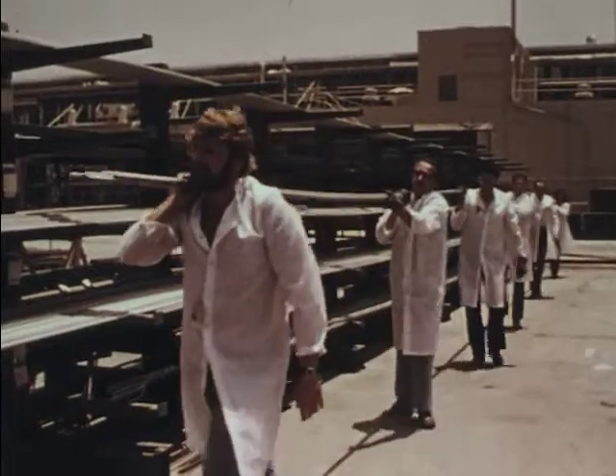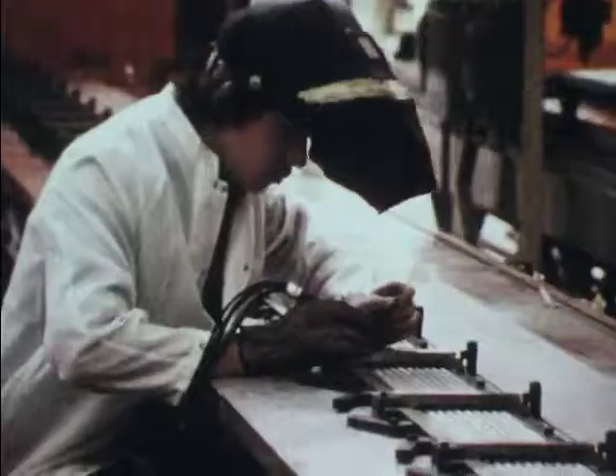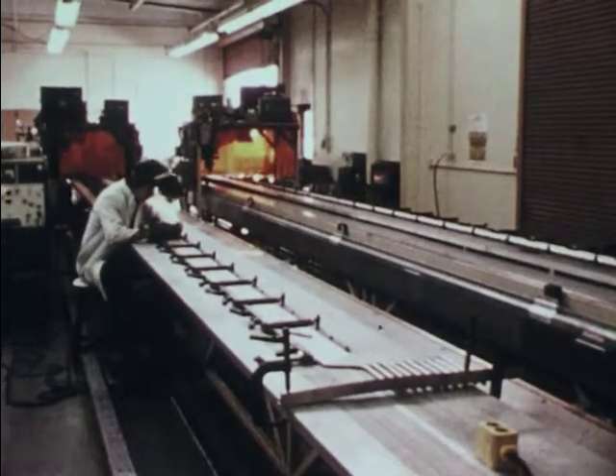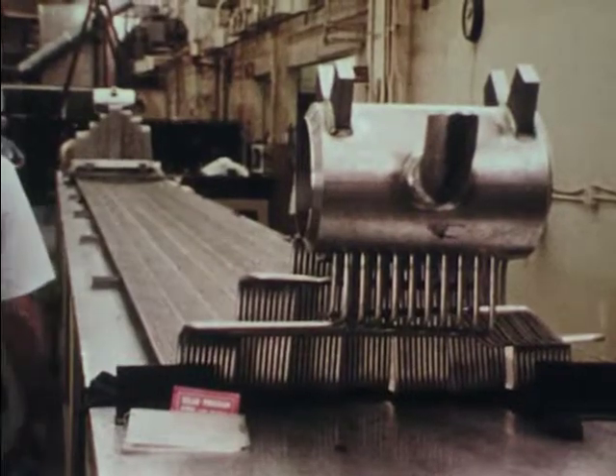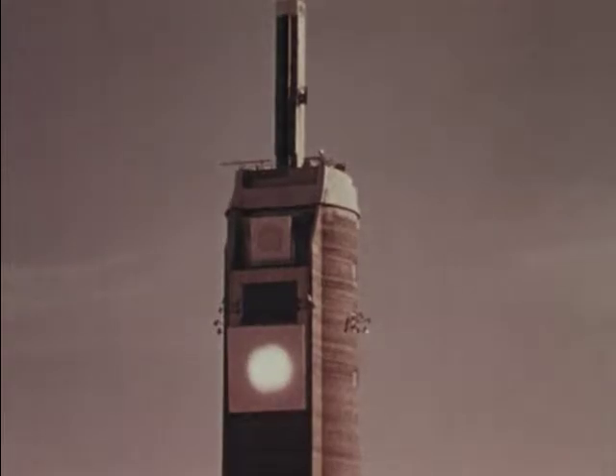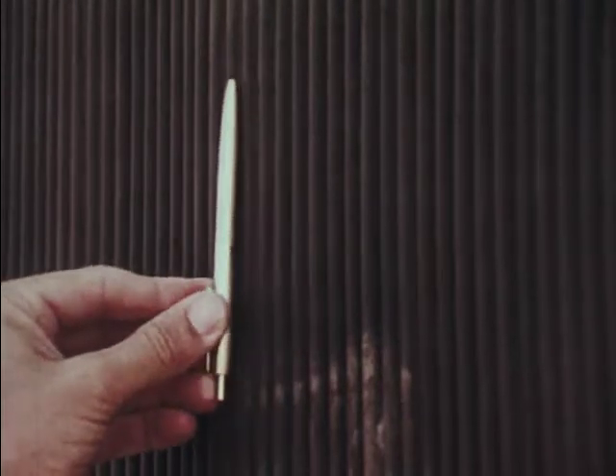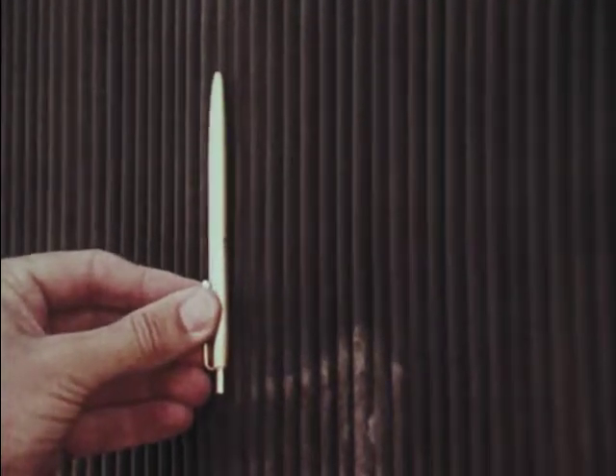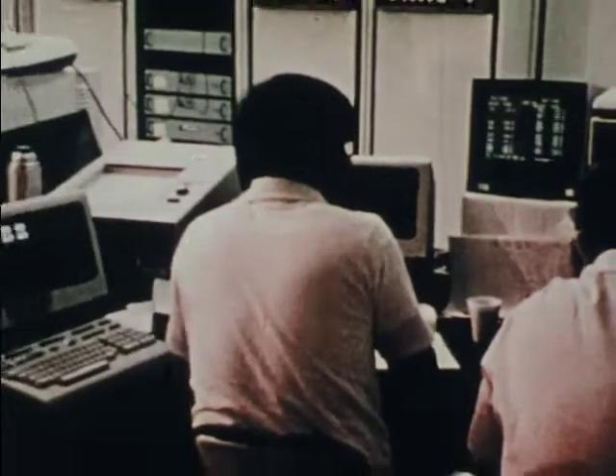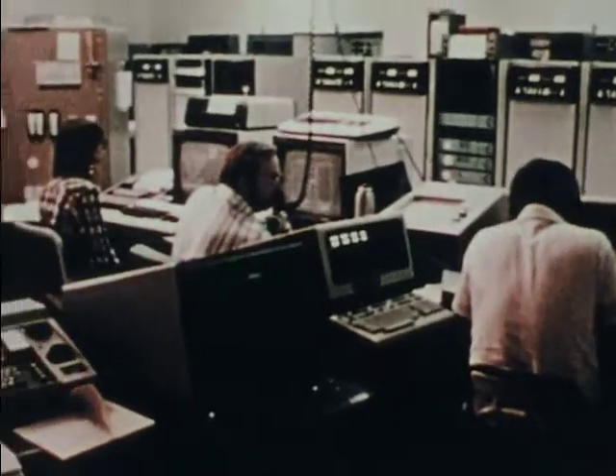The solar energy receiver is made of 24 sets of water-carrying tubes. Their heat-resistant alloy can withstand temperatures ranging from freezing to 1,000 degrees Fahrenheit. The receiver water tubes are also tested. These are coated with a special black paint which absorbs maximal quantities of heat. Receiver sensors report tube temperatures to a computer. Water flow is then adjusted to carry off the heat, maintaining the system's steam temperature and pressure levels.